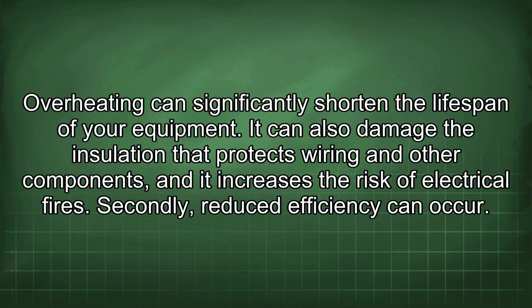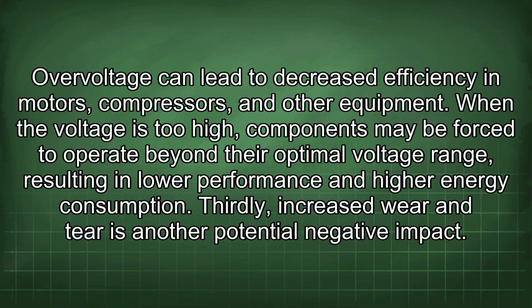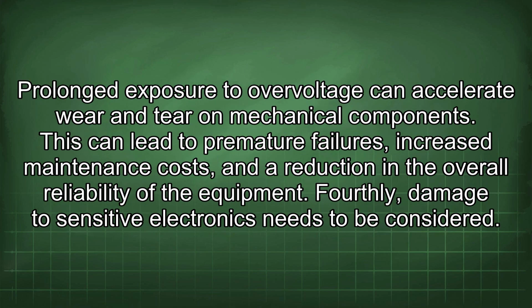Secondly, reduced efficiency can occur. Overvoltage can lead to decreased efficiency in motors, compressors, and other equipment. When the voltage is too high, components may be forced to operate beyond their optimal voltage range, resulting in lower performance and higher energy consumption. Thirdly, increased wear and tear is another potential negative impact. Prolonged exposure to overvoltage can accelerate wear and tear on mechanical components. This can lead to premature failures, increased maintenance costs, and a reduction in the overall reliability of the equipment.